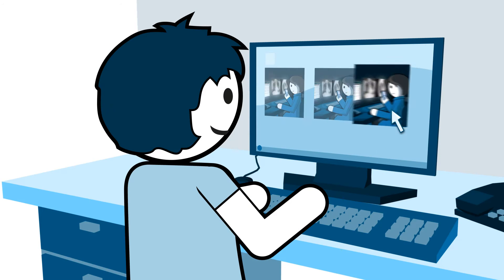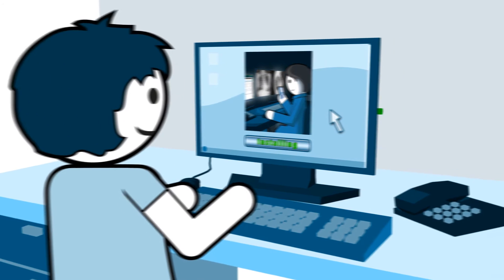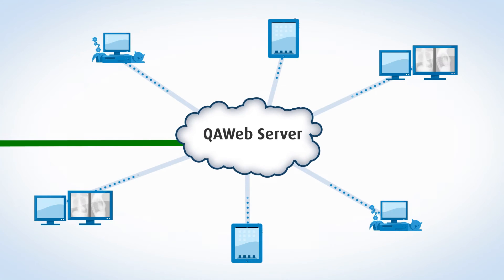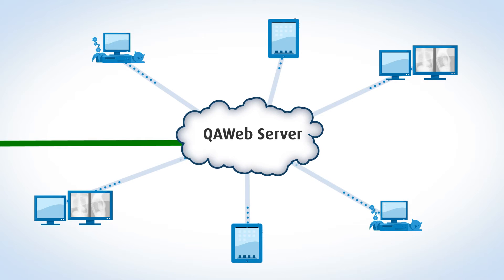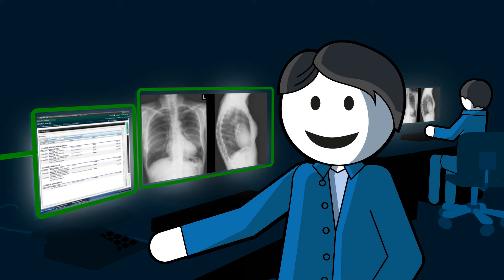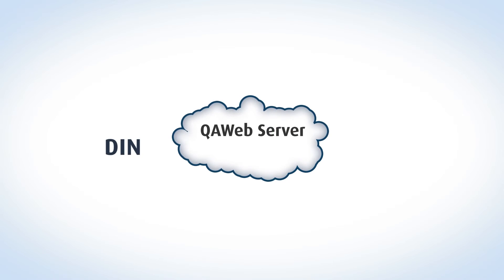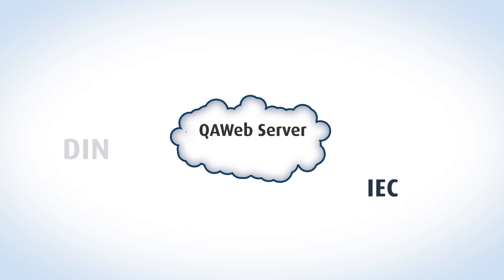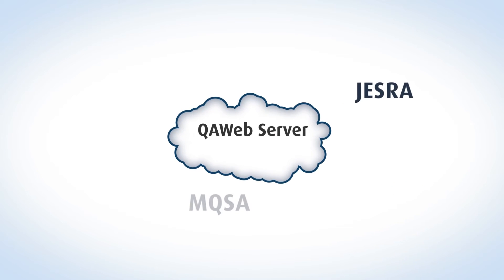After installation, which can be done remotely, Medi-Cal QA Web automatically detects all medical displays throughout the hospital enterprise. The system then performs automatic calibration and compliance checks without interrupting workflow. Thanks to auto-healing, Medi-Cal QA Web even makes necessary adjustments in real time, ensuring compliance with medical standards at all times.